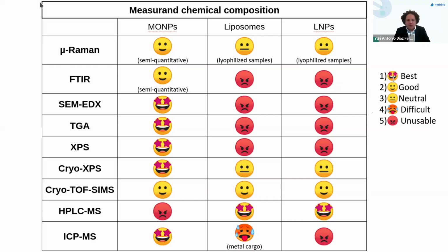One example that is also widely used, although it's still being developed as we speak, and we expect that in the coming years it will be even better, is using ICP-MS to analyze single particles. The instrumentation has been pushed to the level of analyzing even single particles, and in this context you can also use single particle ICP-MS to measure particle concentration, because you count the events in the ICP-MS.